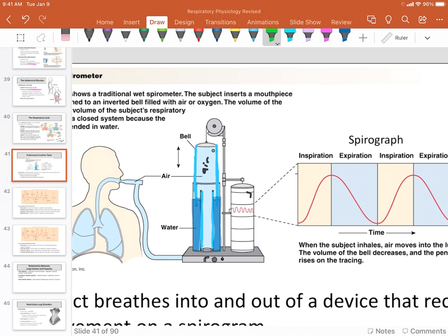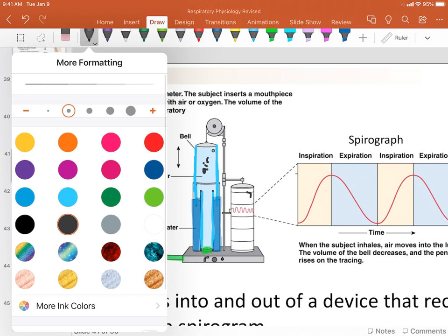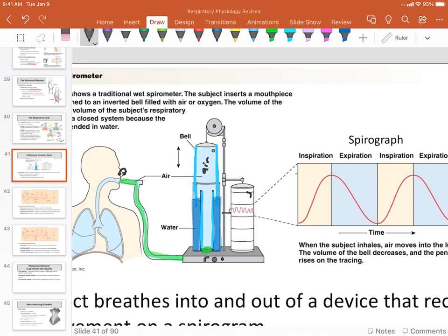The chamber would be inverted so that it floats on top of water. You can actually see this water - I'll color it in darker right here so you can see it. Now notice that we have a tube here. We have this respiratory tube that is connected to our patient. Our patient would form a tight seal over that tube with his or her mouth. Generally speaking, they would either plug their nose or wear a little plug on top of the nose so that air cannot go through the nose and all airflow must be through the mouth. This individual would then breathe in, and with each inhalation they would draw air in from the bell.